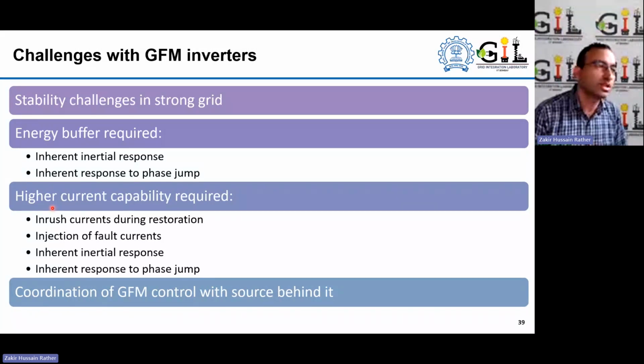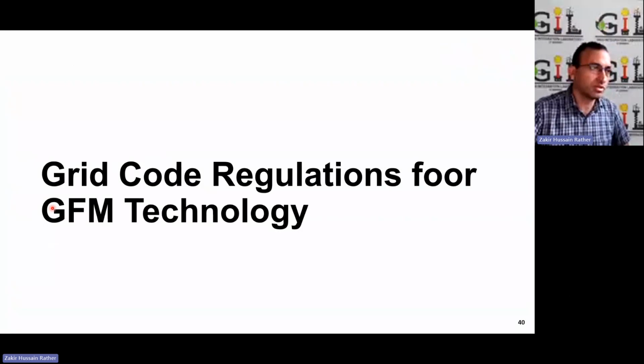There are methods to control the current output of the grid forming technology, but because it is voltage source technology, similar to a conventional generator, there is an initial current that can overshoot the rating of the converter. You could say the converter switch current rating needs to be higher than what may otherwise be required in the grid following control topology. And coordination of grid forming control with the source behind it, particularly if it is a mechanical system in a wind turbine generator, all those complexities are there.